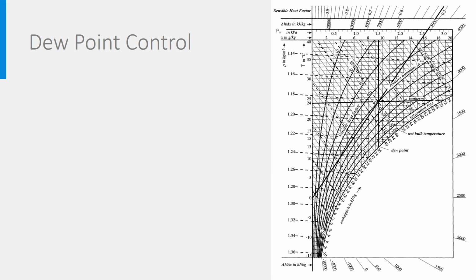So let's talk about dew point control and visualize it on the Mollier diagram. First, it is good to realize that in a hot and humid climate, hydronic cooling may not be the most efficient method because of the shape of the Mollier diagram. For instance, at 35 degrees and 50% humidity, the dew point is 23, while if the humidity is only 20%, we can cool down to 8 degrees without condensation.